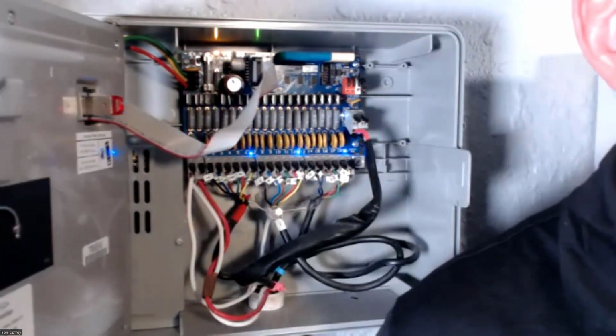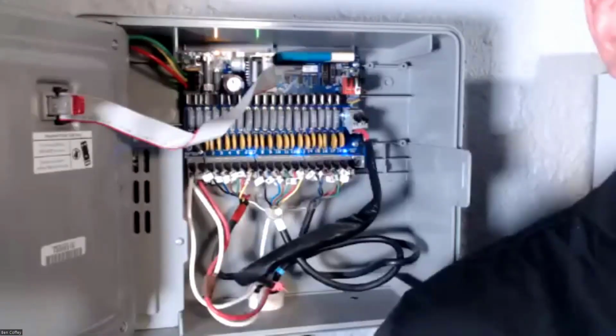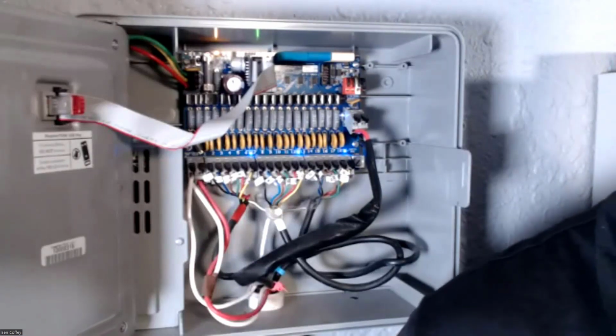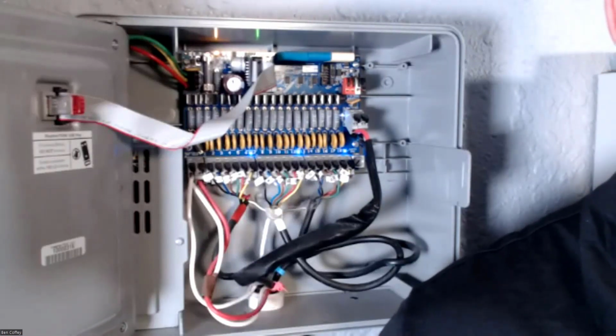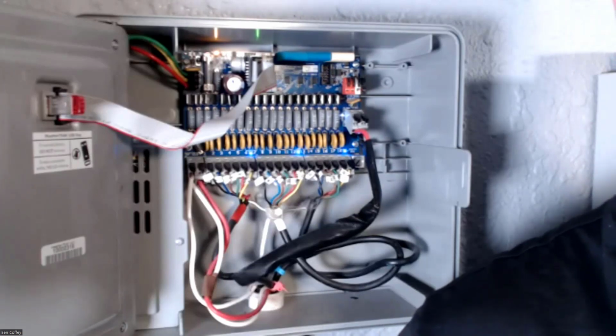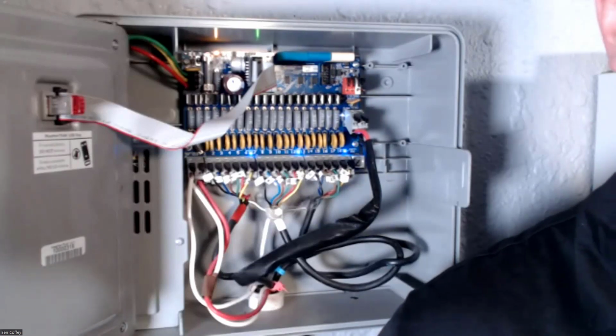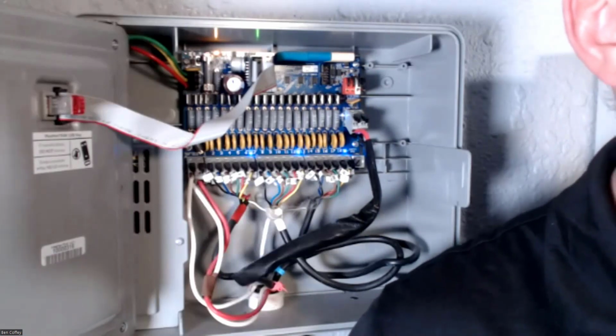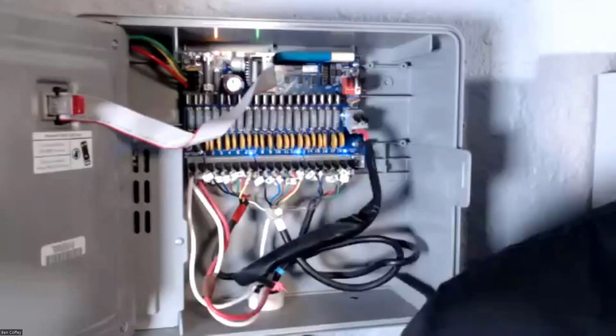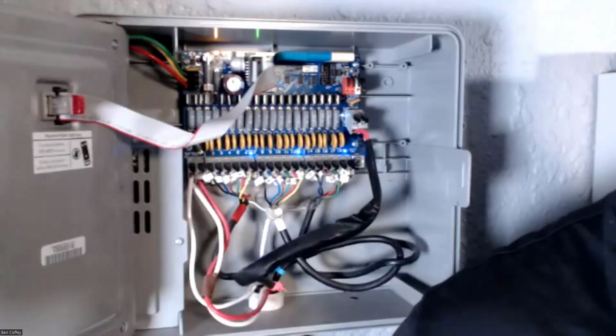Maybe multiple shorts over time on the valve wires would cause a fuse to potentially blow. A direct short in the field would definitely do it too. I also see anomalies from the power side, like anything coming in from the transformer. That's really what the fuse is designed to protect against - if we're in an area of brownouts or some sort of anomalous or dirty power surge happens. That's what I see most frequently blowing fuses.